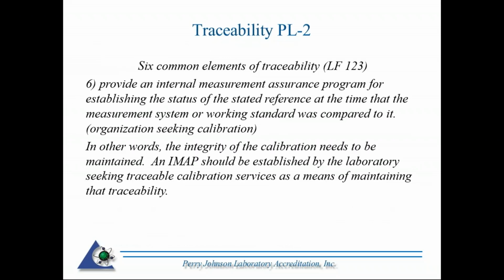And last but not least, and this is confusing when this is read, it references another internal measurement assurance program. This is actually in regards to the lab that is submitting the artifact to the non-accredited lab. They need to have an internal measurement assurance program themselves in regards to the measurement that device is being used for. So if you are accredited, that would be known by the PJLA assessor, so that there are requirements for equipment's intermediate checks. That should be covered under the assessment.